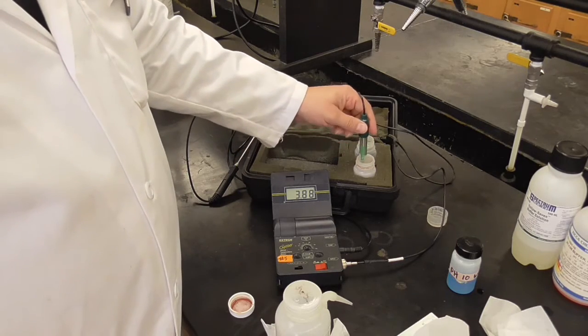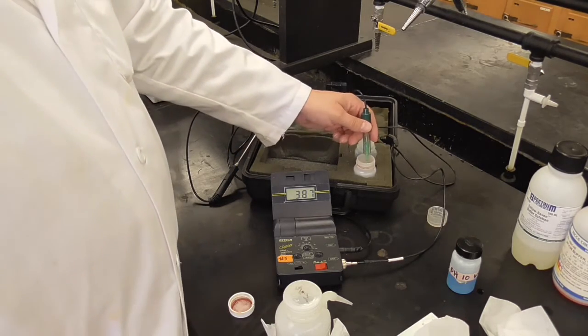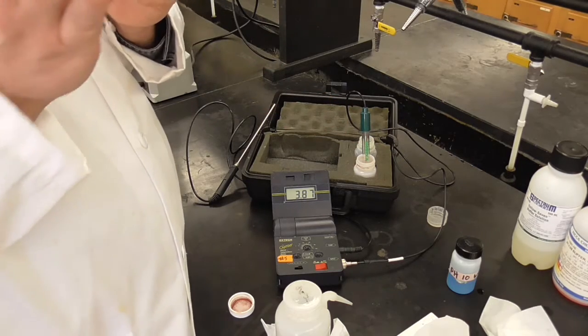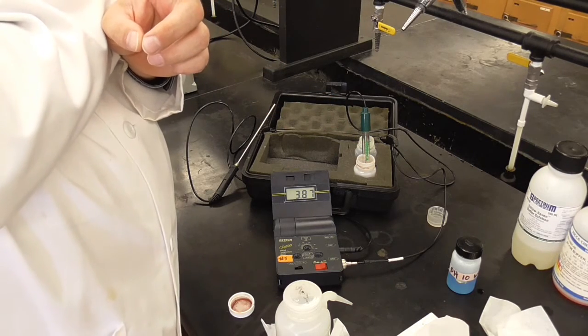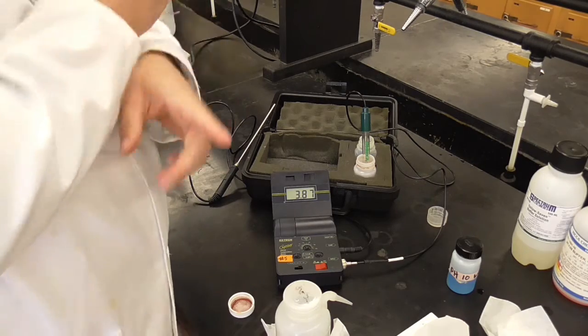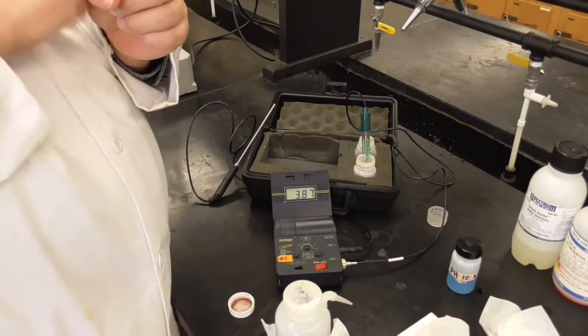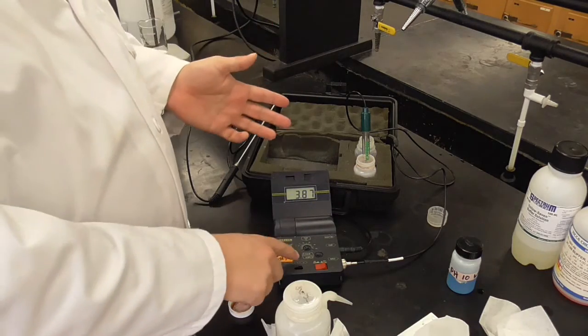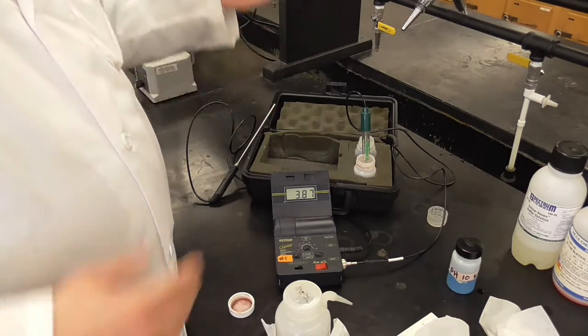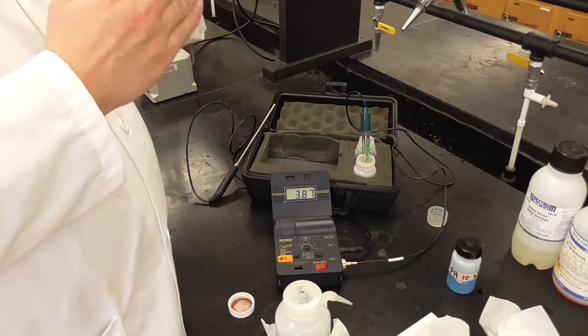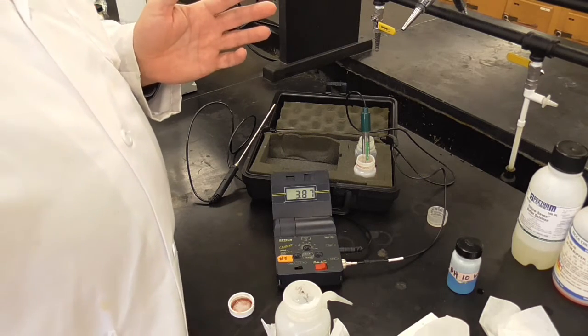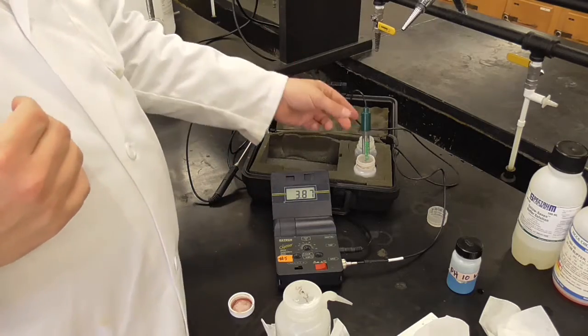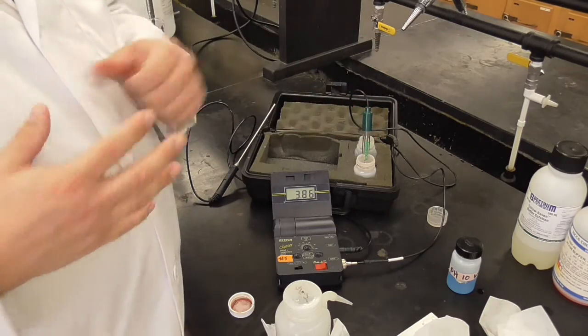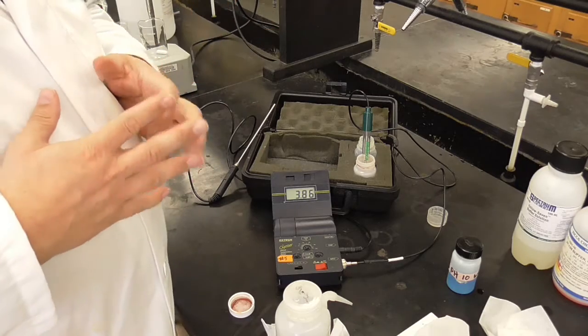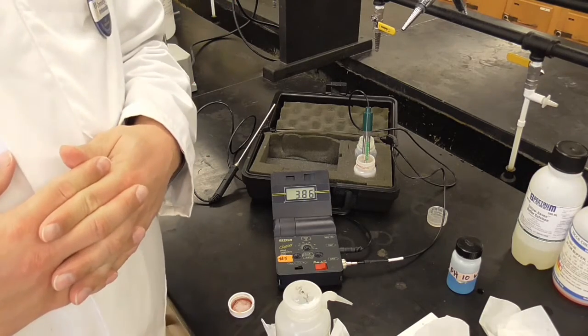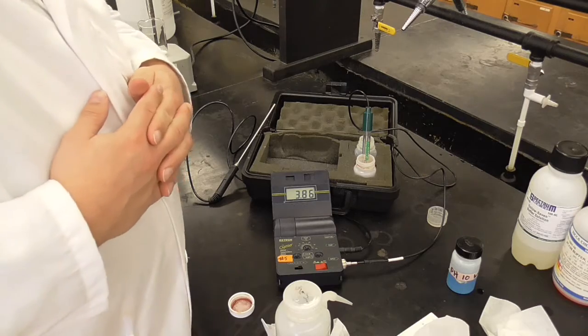You're saying, wait a second, shouldn't that read pH 4? Yes, it should. But remember, where we calibrated at 7 and 10, we're way down at pH 4. Right? So it's not nearly as accurate away from the second calibration point. So if I were doing acids, I would use the slope button to put this at 4, and then I'd be much more accurate at low pH. But if I got really high pH, it's not going to be quite as accurate. I mean, it's still pretty close, but it's not going to be as accurate. So that's why you want to choose the second buffer depending on what your application is. Okay?